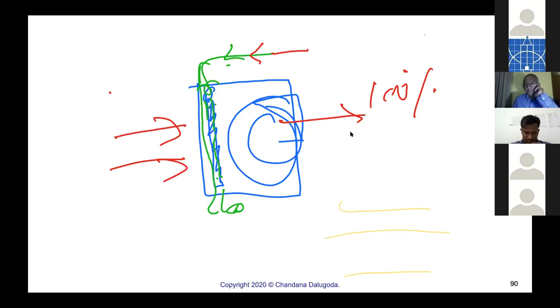Number two, on coil selection, as you very correctly said, the 13 degrees coil condition or dew point condition should be met by the cooling coil. Say we generally need 12 degrees coil conditions. From my experience and the exercise on this particular project, the same off coil condition that you make with a 7/12 coil in the conventional design can be met with a 7/14 coil. 7/14 is what we practiced in the project you raised. How do we understand that? I also got confused, taking 14 as the return. How can you make 13 or 12 degrees off coil?